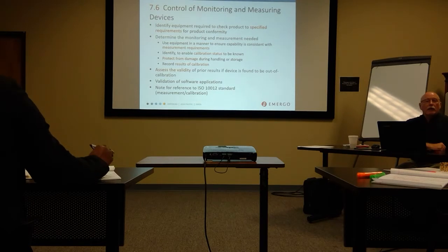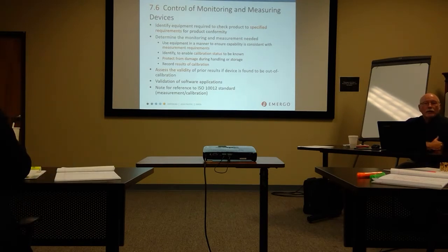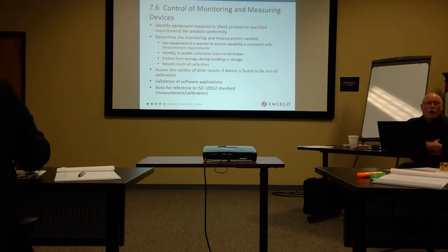So I have to identify the equipment. At what frequency do I calibrate this? There is no prescribed table of frequencies or anything like that, it's based on your experience. What are you using this for? It's a risk decision, again, how critical is it? If it goes out of calibration, then what? What's the impact of that? So at some frequency, usually annual, sometimes more frequently than that, depending on what we use this for, I send this out, the calibration vendor does their thing, sends it back to me with a certification that says it's calibrated.